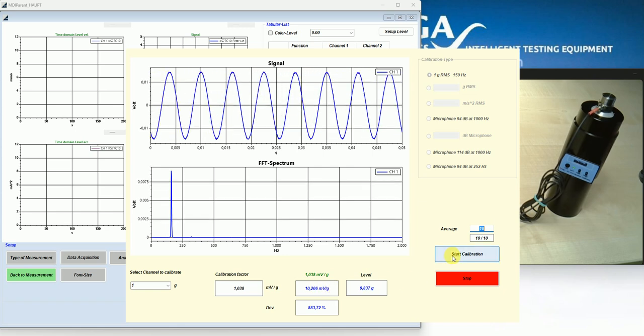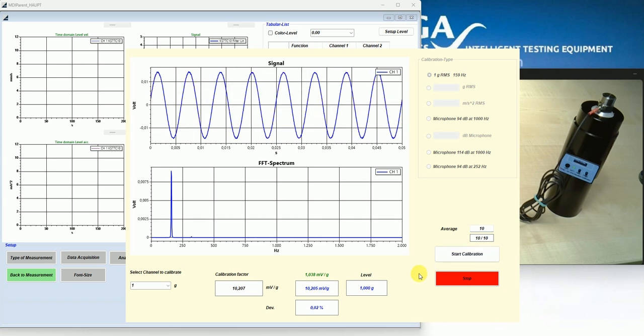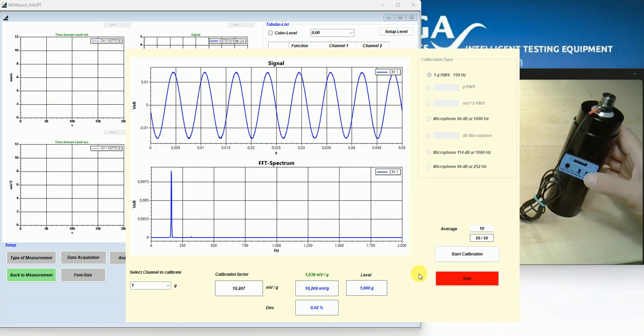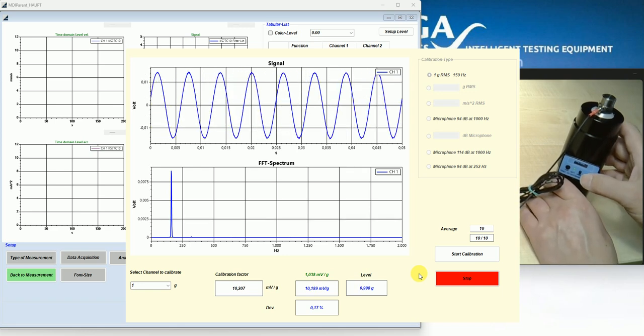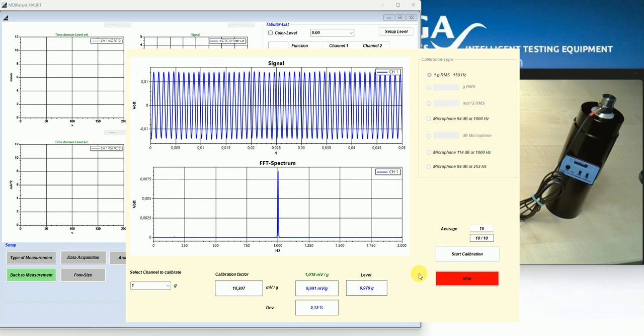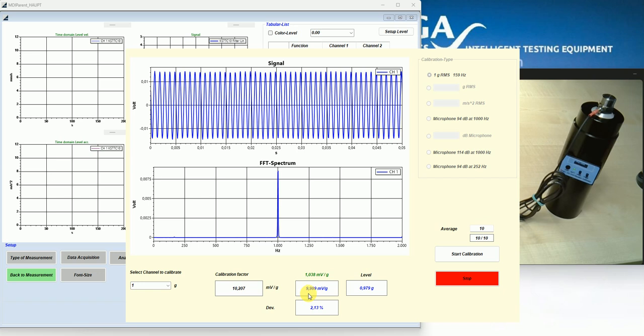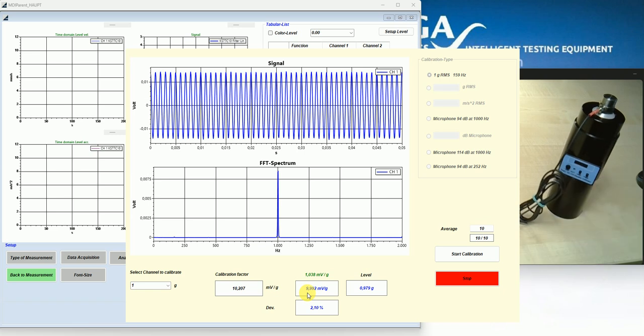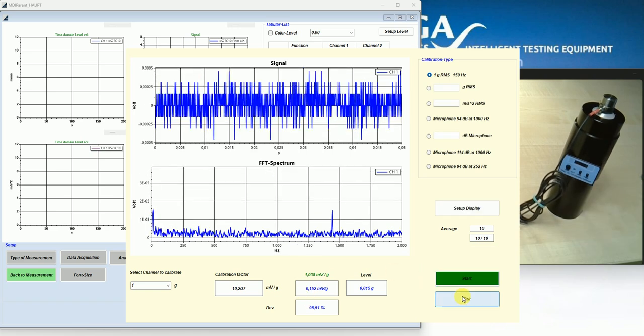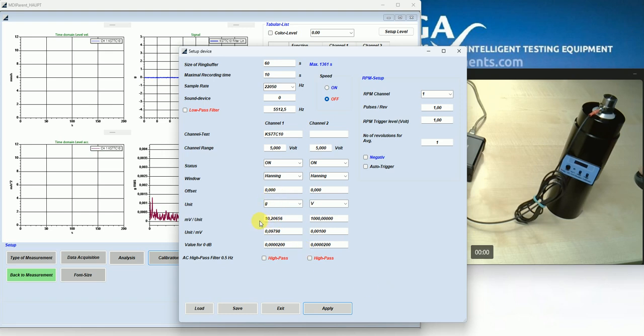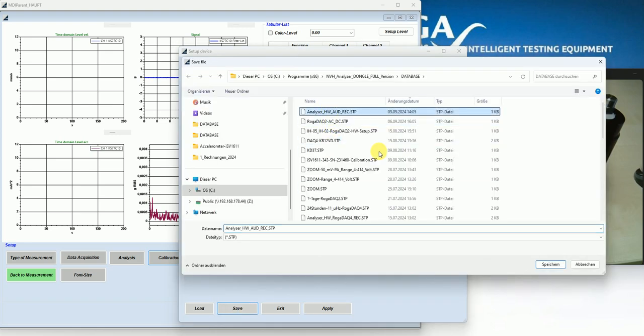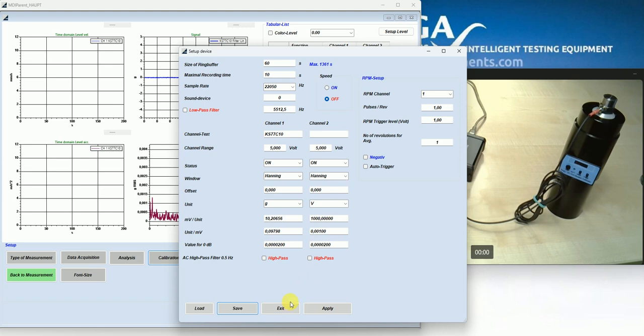Now I can again execute the calibration. So this is done. With this calibrator I can also change the frequency, for example. Now I see that at 1 kilohertz I have 9.9 millivolt sensitivity per G. Here it is again noted. I save it, and this is done.